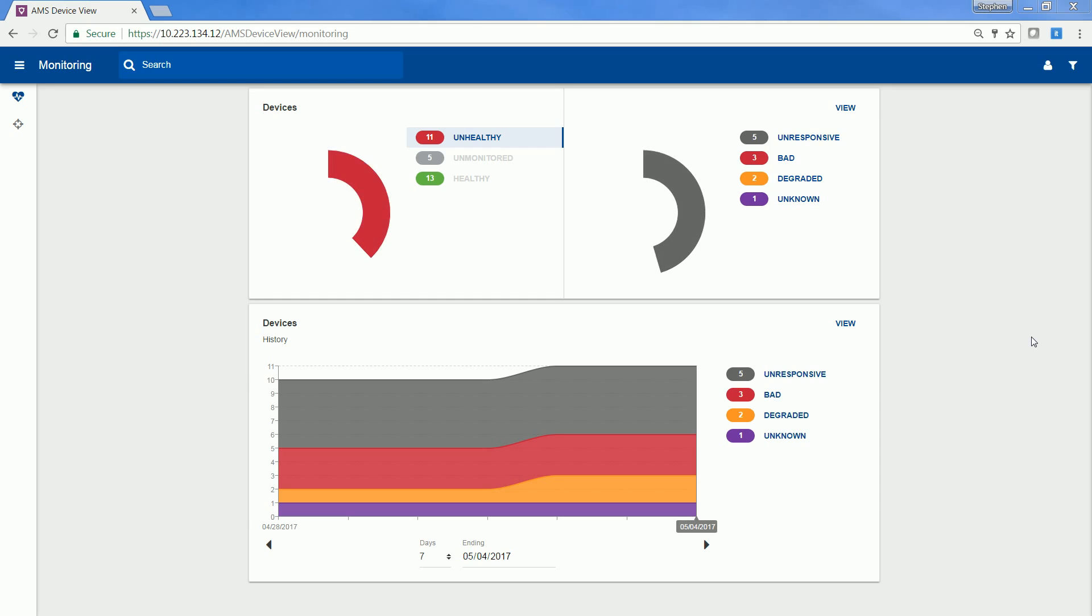The top-right pie chart breaks down the unhealthy devices by the NE-107 recommendations, which breaks down the device alerts in terms of severity. These device alerts come from onboard diagnostics of the device themselves, programmed in by the device manufacturer. The four severities are unresponsive, failed, degraded, or unknown.